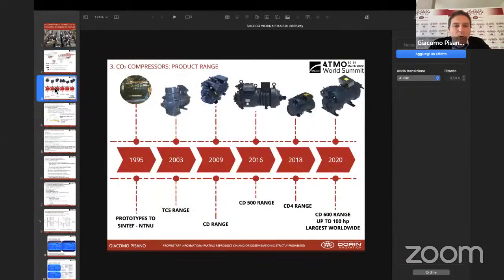A little bit on our CO2 journey. In CO2, basically, we started first developing CO2 transcritical compressors. We delivered the very first piece of equipment in 1995 to Gustav Lorentzen's team in Norway, where they were validating the use of CO2 with floating head pressure. They have basically been reinventing modern CO2 refrigeration. And then after this very old piece of equipment, we have been placing into the market more and more compressors from various platforms. And in 2020, we launched into the market our flagship compressor, the largest transcritical compressor actually available in the market.